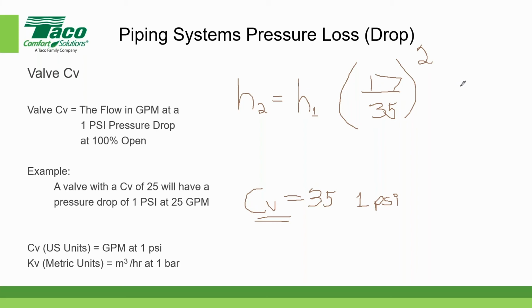Hold on one second. I've got to get my handy dandy calculator out here. So 17 divided by 35 is approximately 0.5. It's a little less than that, squared, multiplied by the initial pressure of 1 pound, and the new pressure is 0.23, we'll call it 0.24 in this case. So the final pressure is going to be equal to 0.24 PSI. Ta-da! Does that answer the question? Yes, it does. That answered quite a few, so that was good. Cool stuff. Okay, erase all this.